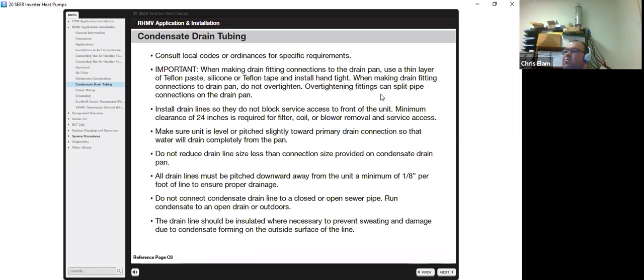It is important when making these drain fitting connections to the drain pan to use a thin layer of Teflon paste or tape and install it hand tight. Don't get in there with channel locks and lay into it. Over tightening the fittings can split the pipe connections on the drain pan, and also be sure not to cross thread. If you do cross thread it and ever have to take it apart, replace the drain pan at that time.